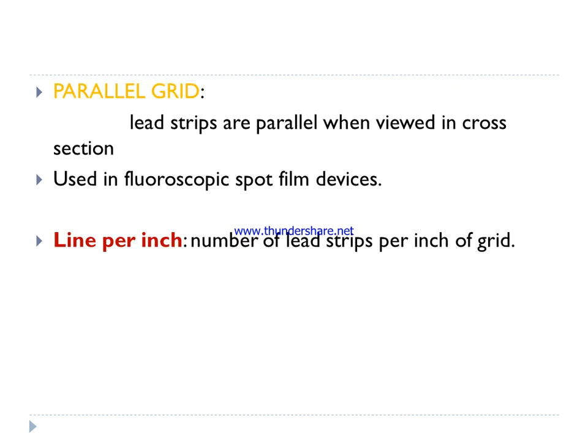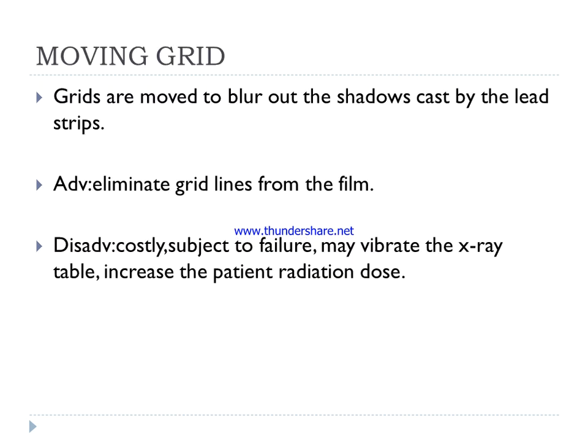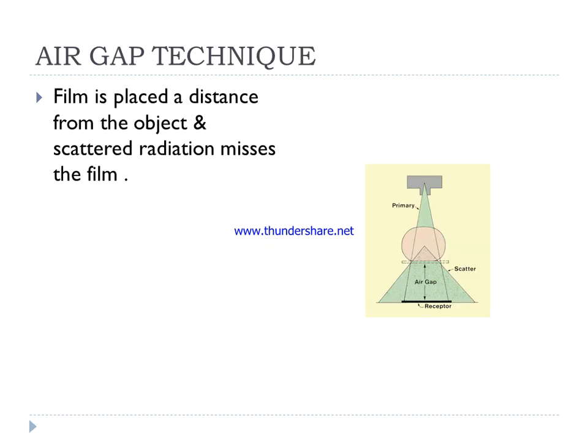A moving grid is mainly used to blur out the shadow cast by the lead strips. The main advantage is to eliminate grid lines from the film. However, moving grids are very costly, subject to failure, may vibrate the x-ray table, and increase the patient radiation load.